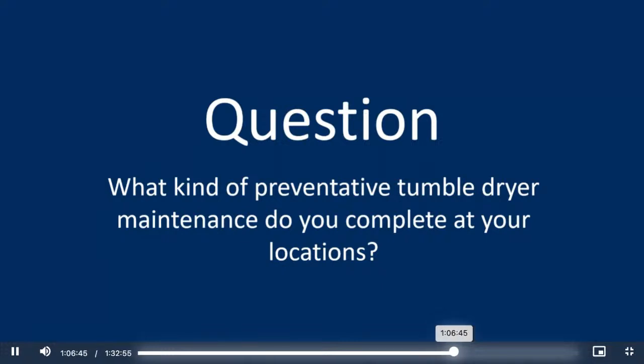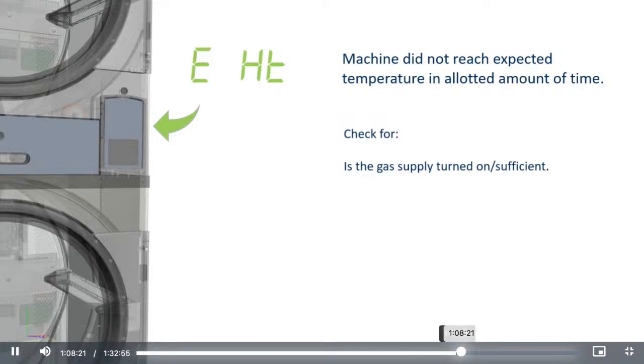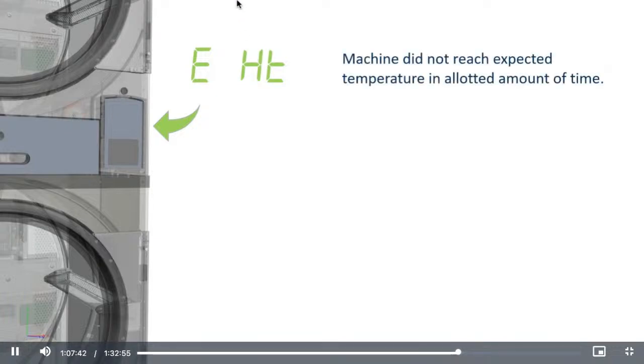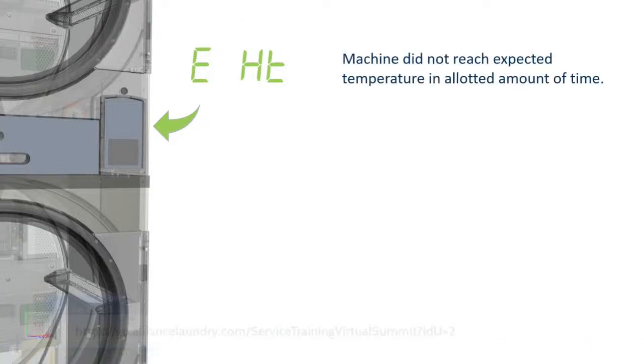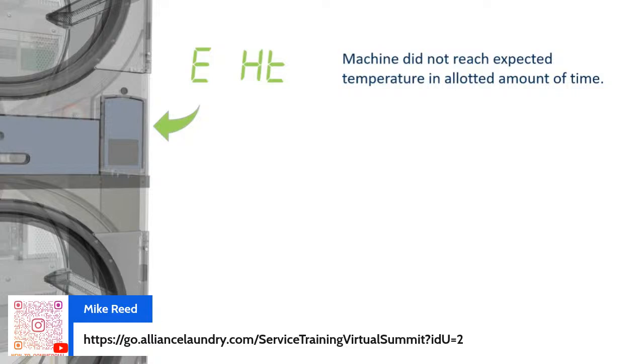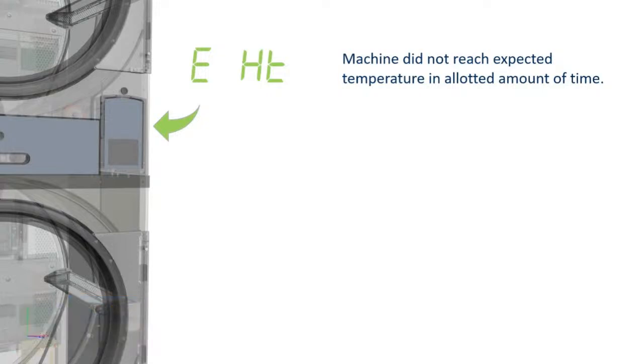A non-OEM part. A store owner called me in a panic: I've got a whole bunch of my machines saying EH. It was like an error heat code. That means the machine did not reach an expected temperature in an allotted amount of time. We knew we were supposed to be heating, the control knew that, so it looks for the temperature to go up within 5 minutes or so, or 2 minutes. If it doesn't, it produces this very generic heat error code.